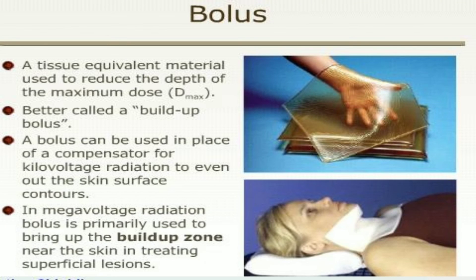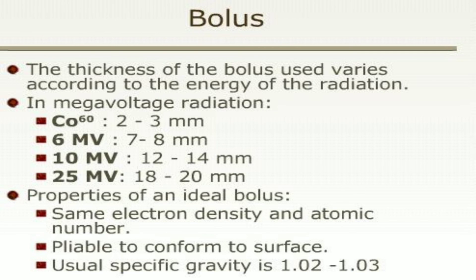Bolus is a tissue-equivalent material used to reduce the depth of maximum dose, also called build-up bolus. A bolus can be used in place of a compensator for kilovoltage radiation to even out skin surface contours. In megavoltage radiation, bolus is primarily used to bring up the build-up zone near the skin in treating superficial lesions. The thickness of bolus varies according to the energy: for Cobalt-60, it is 2–3 mm; for 6 MV beam, 7–8 mm; for 10 MV beam, 12–14 mm; and for 25 MV, 18–20 mm.